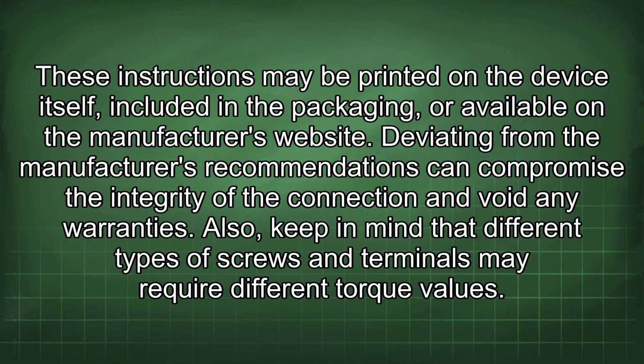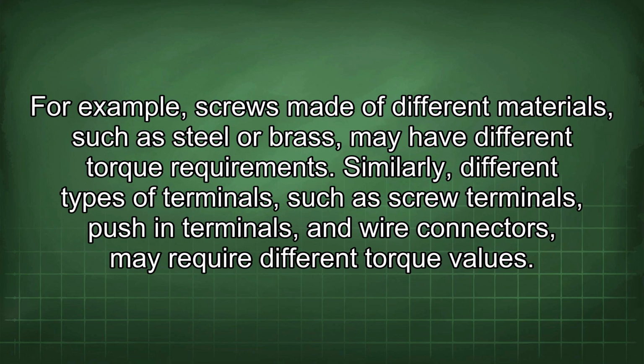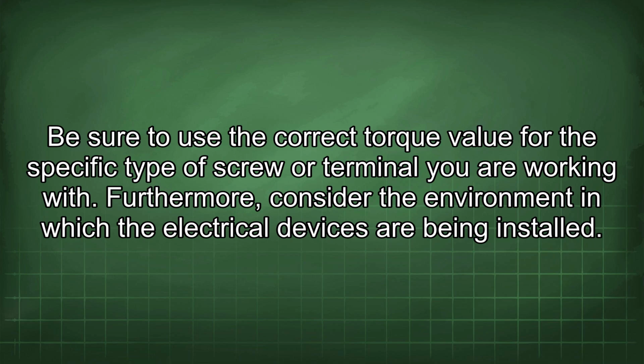Also, keep in mind that different types of screws and terminals may require different torque values. For example, screws made of different materials, such as steel or brass, may have different torque requirements. Similarly, different types of terminals, such as screw terminals, push-in terminals, and wire connectors, may require different torque values. Be sure to use the correct torque value for the specific type of screw or terminal you are working with.